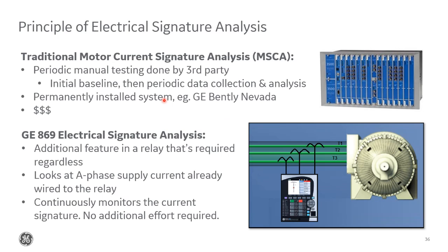So the idea with us integrating the ESA concept into the 869 is not necessarily to replace either of these options. Again, these traditional current signature analysis systems are very detailed. But if you already have or will be putting in a motor protection relay like an 869 anyway, adding just a software option to something you'll be installing regardless is probably much more convenient and cost effective. So we in the 869 look at the phase A current that's already being brought to the relay. There's no additional wiring or installation requirements, just the software option adder and a few extra settings.